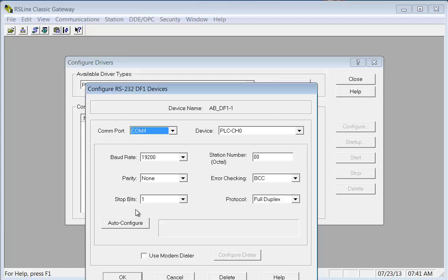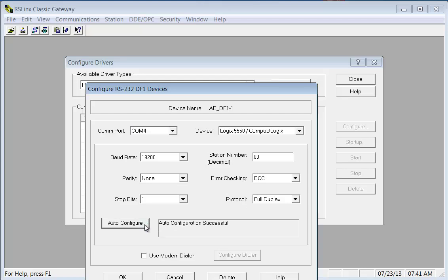I'm assuming because when I hit configure driver, RSLinx is going to start sending out messages out of that COM4 port, and if it doesn't hear anything back right away, within literally milliseconds, it will change one characteristic, one of these parameters, and send it out again. When it finally does get a message back, it's Aha! I've got the right format. So auto configure. That was too fast. Auto configuration successful. Now that's never too fast when you're in the field and the production manager is standing leaning over your shoulder wondering what you're doing.